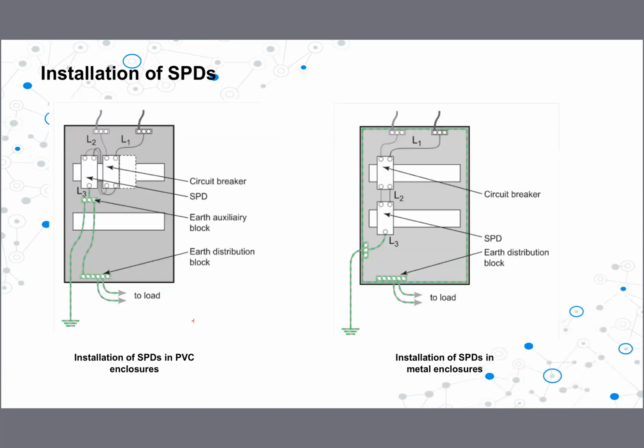So then let's look at the installation methods of SPD. Now we are coming to the end of the presentation. I have only a few more slides, maybe maximum 5-10 minutes. When we install an SPD, if it is a PVC enclosure, PVC doesn't conduct, so you need an additional earth terminal near the surge protection device to reduce the cable length, right? If it is a metal enclosure, you can install it this way. First, a circuit breaker to give overload protection to the SPD, then below that you can install the SPD, then you can connect it to this earth terminal, right?